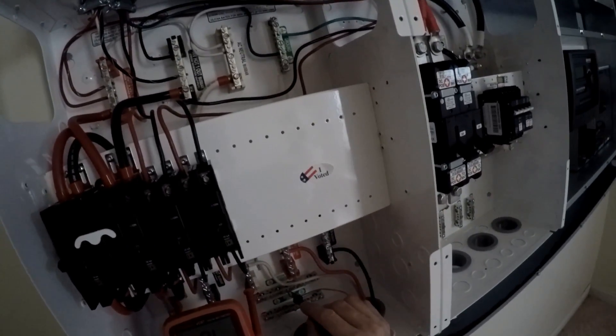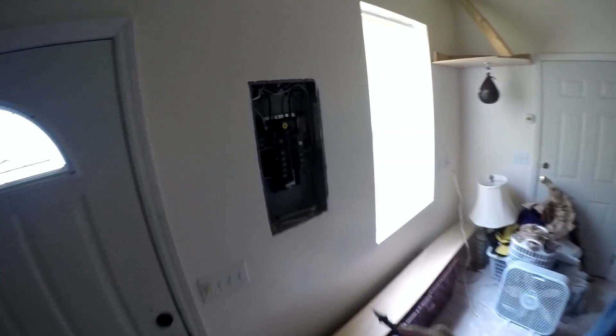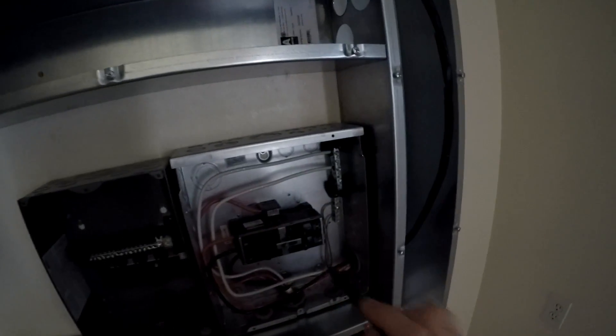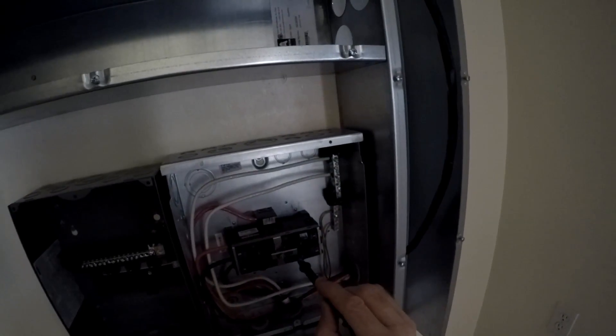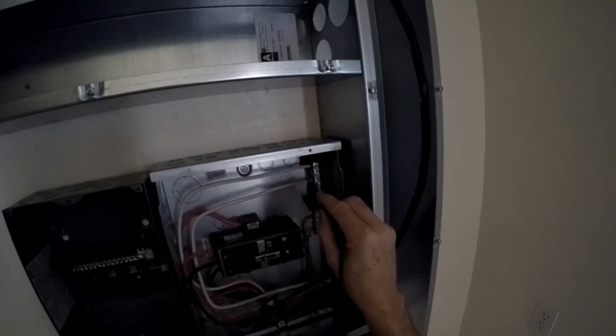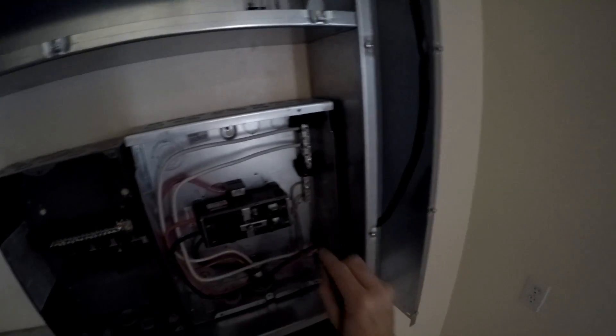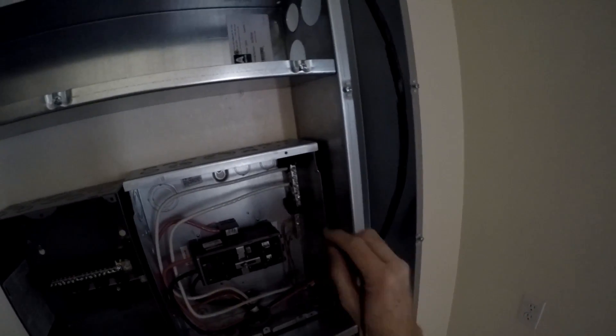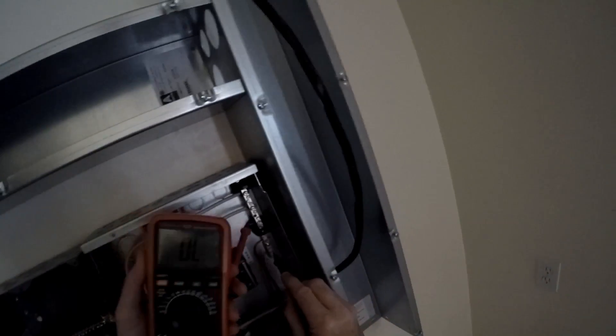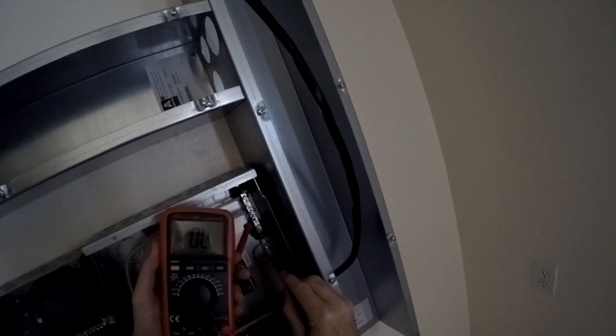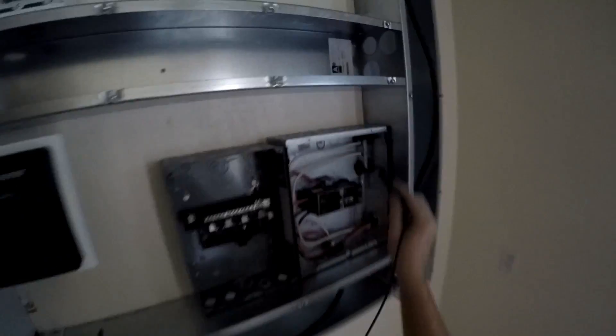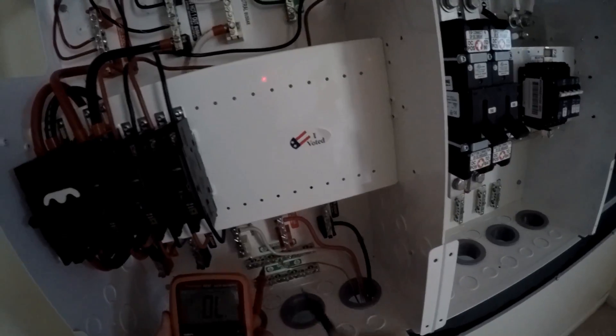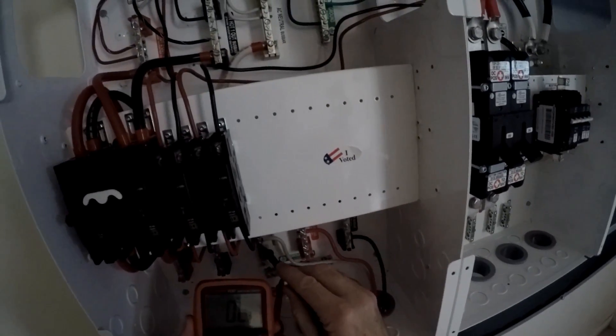They were not connected, but since now I've connected my main power line from that breaker over into this transfer panel, that brings that common and ground are now connected here. So these are now gonna be tied. They're tied here and they're gonna be tied here.